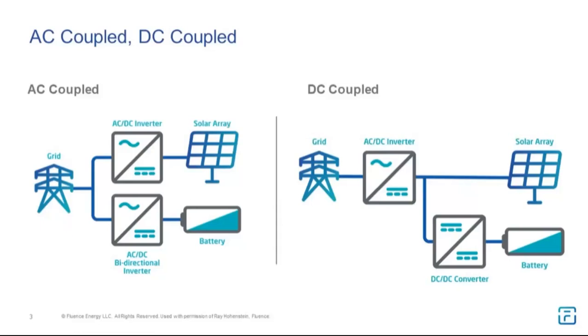Also, a point I'll dwell on later, is what California calls resource adequacy, or what's commonly called capacity value elsewhere. If you're getting a capacity value for the batteries of a certain amount, does that mean you have to retain that capability reserved for deliverability at your point of interconnection all the time? That throws away a lot of the value of even thinking about a hybrid. Why would I save 60 megawatts out of the interconnection for the battery to get capacity value, when I've got 100 megawatts of PV there that I can't deliver most of the time? And then, of course, you have to be able to charge from the PV to the batteries in various ways, which also gets complicated.